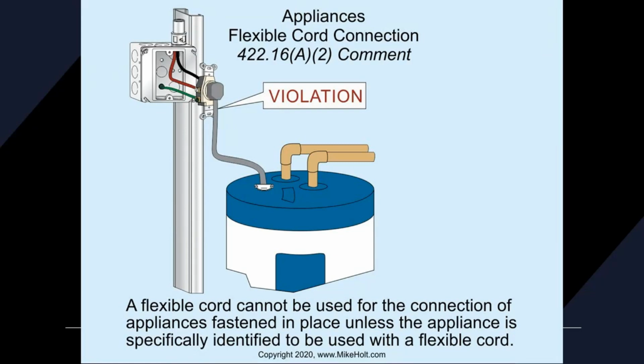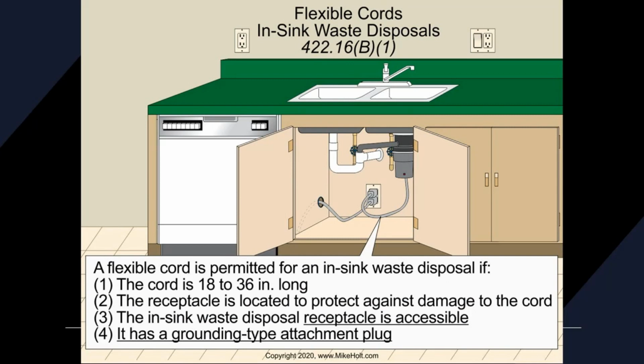All right. Flexible cord cannot be used for the connection of appliances fastened in place unless the appliance is specifically designed to be used with a flexible cord. Okay? They want that thing hardwired. There's a good illustration of what's going on there. Flexible cords and in-sink waste disposal. This is another little code section that's on about every test. A flexible cord is permitted for an in-sink waste disposal, and here's the kicker, 18 to 36 inches long.